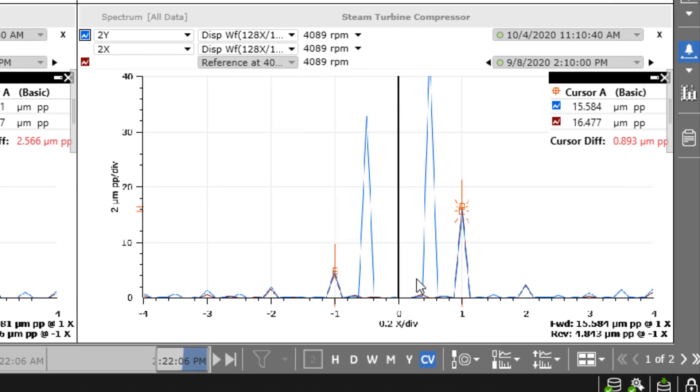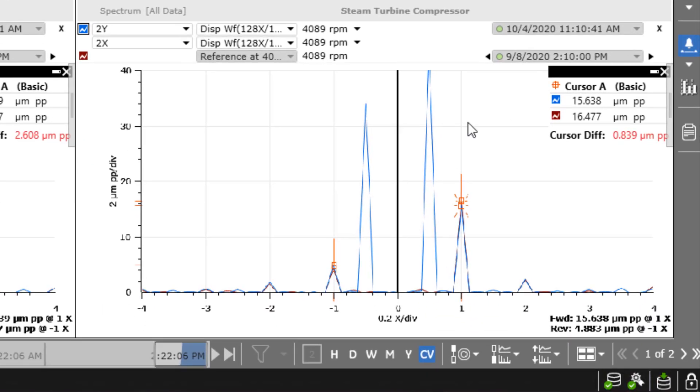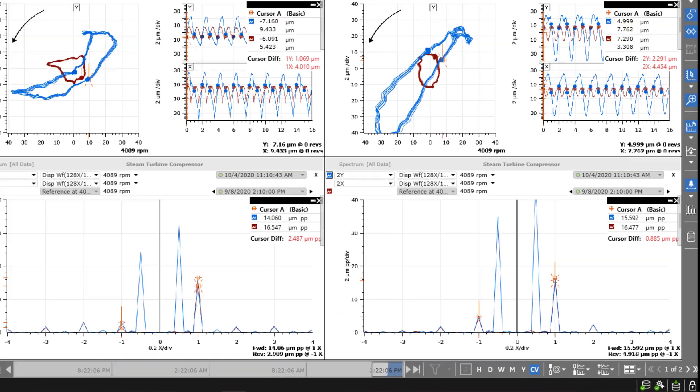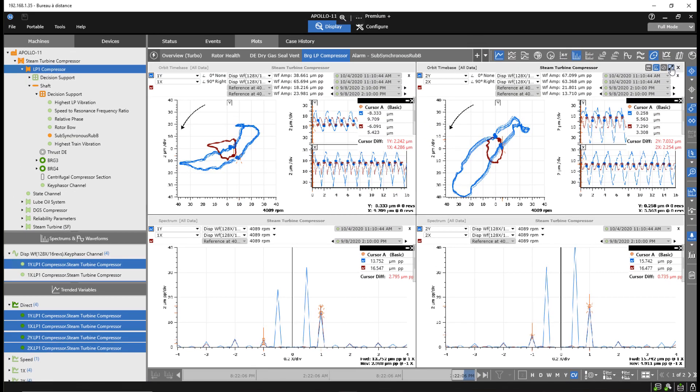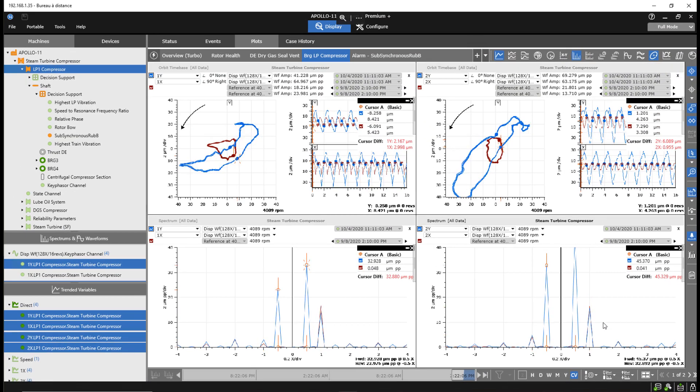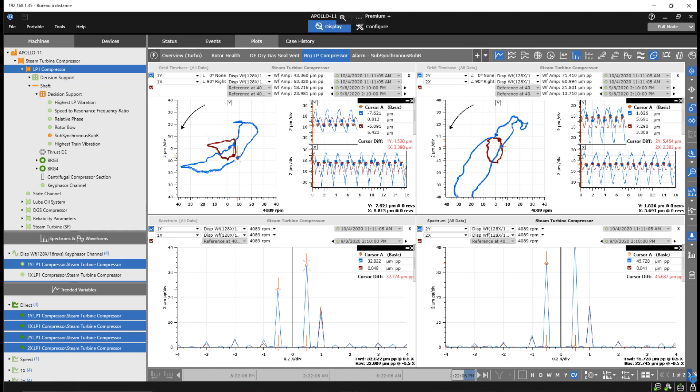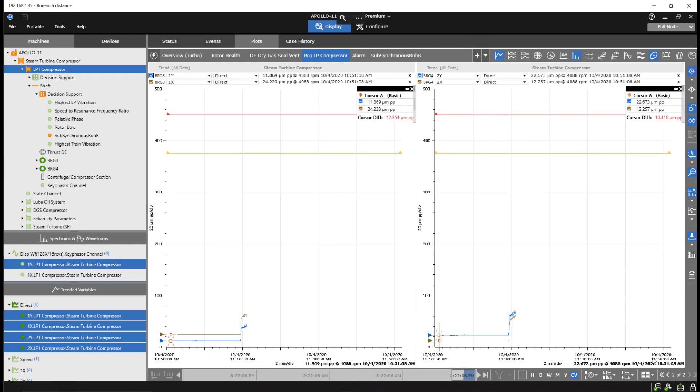The engineer also reviews spectral data and confirms the presence of half-X behavior. The engineer then compares the corresponding direct vibration trend values between bearing one and bearing two.